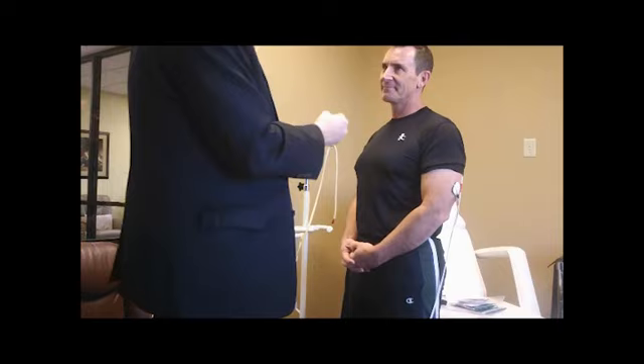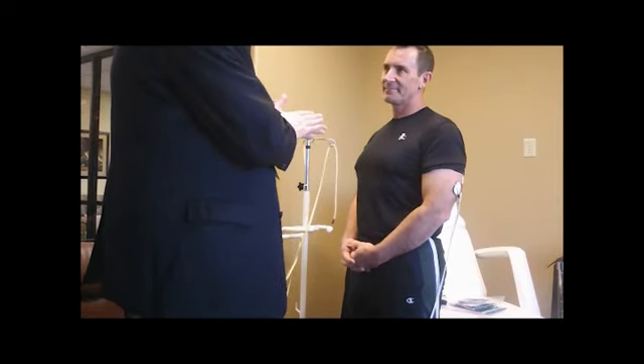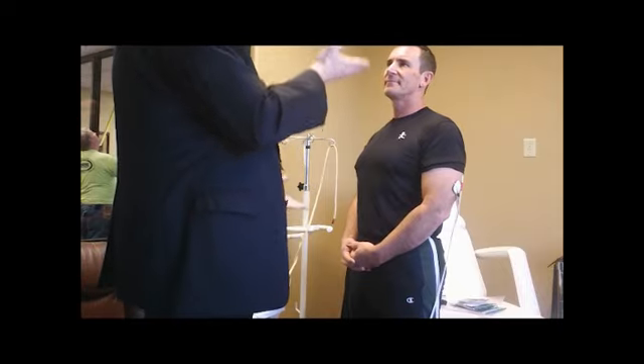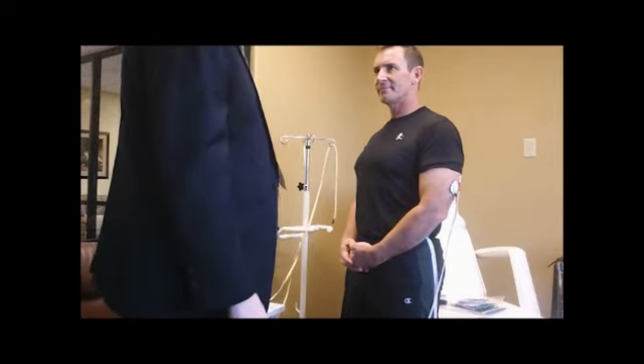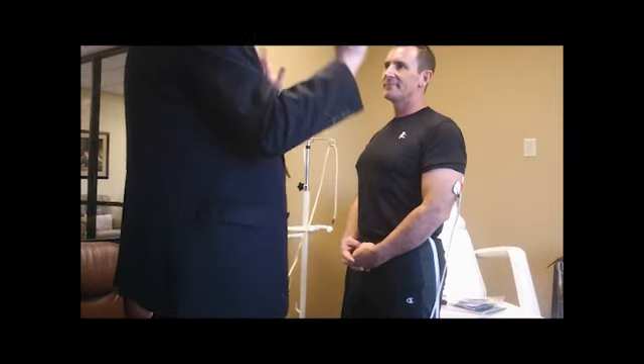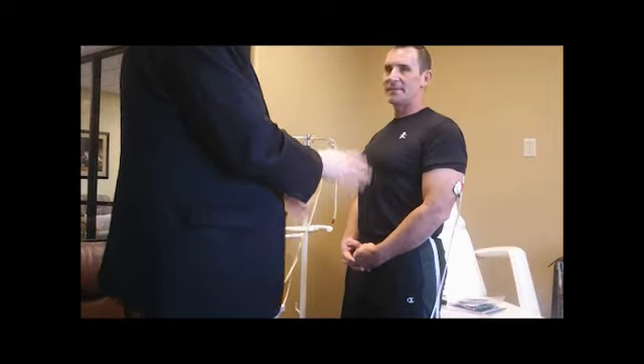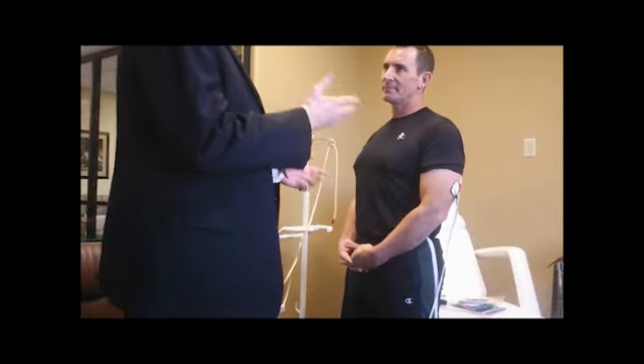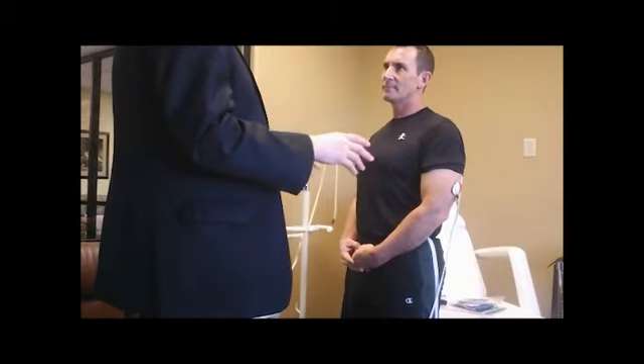When you get massive muscle contractions, we can actually increase the girth of the thighs for stroke patients by 10 inches over an eight-week course of therapy. I don't know of any other device that can do that. The DC output systems, to get the high voltage — which is what causes the contractions — they raise the amperage up. And once you go above 10 milliamps it becomes very uncomfortable, so you can't take it for a long period. What we need is better compliance and tolerance among patients to tolerate full resistance exercise for extended periods of time. The compliance and tolerance increases when you have lower amperage — there's a direct inverse relationship there.